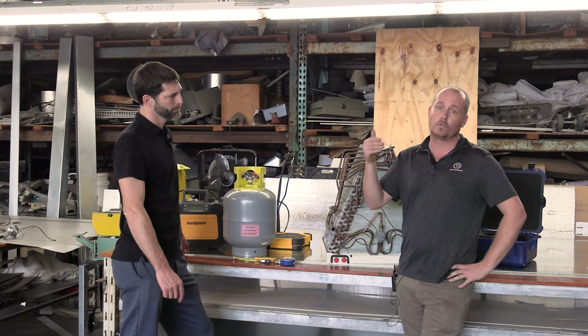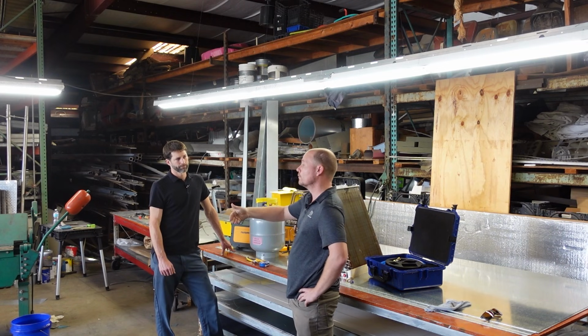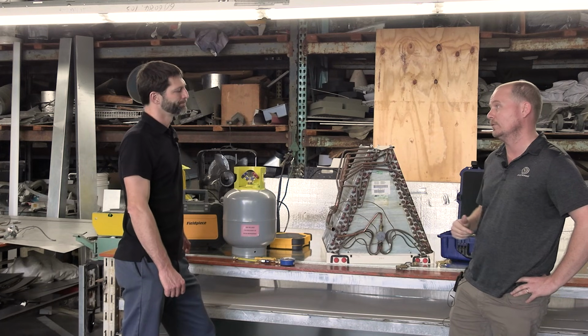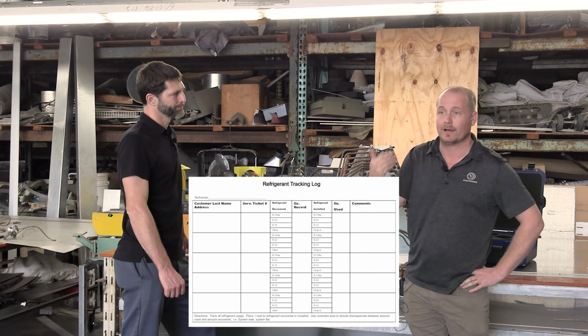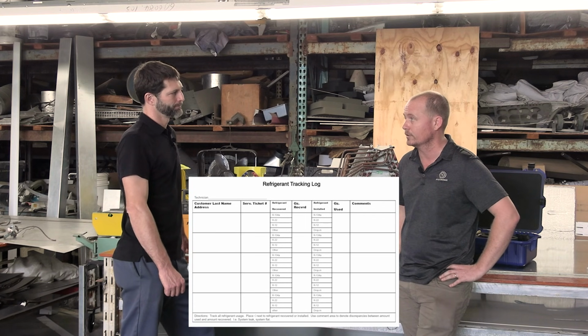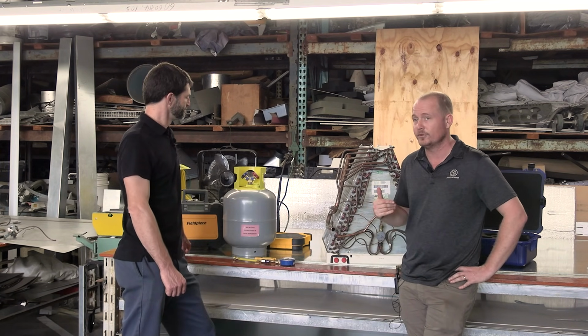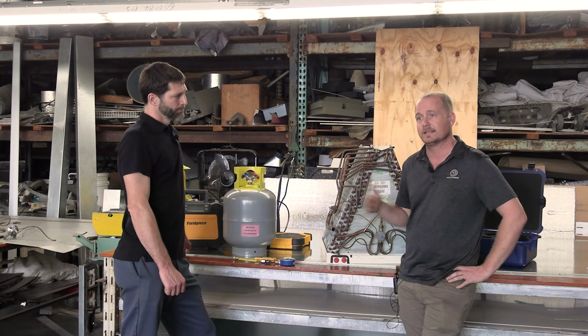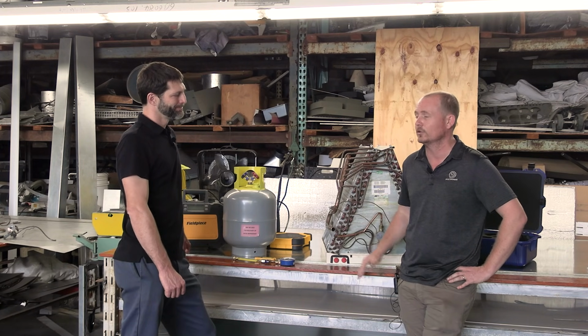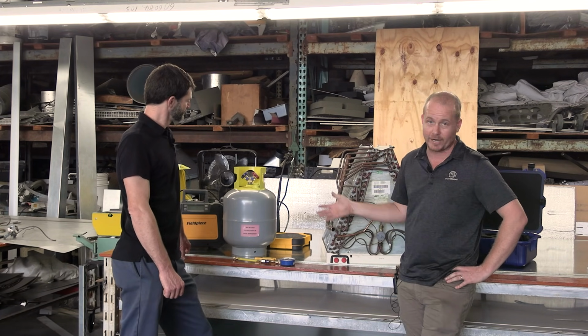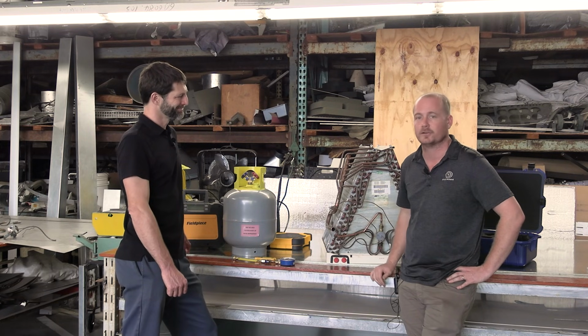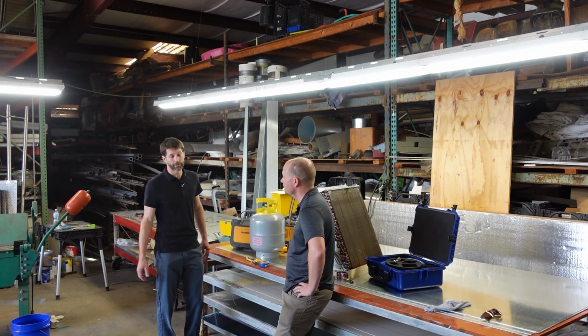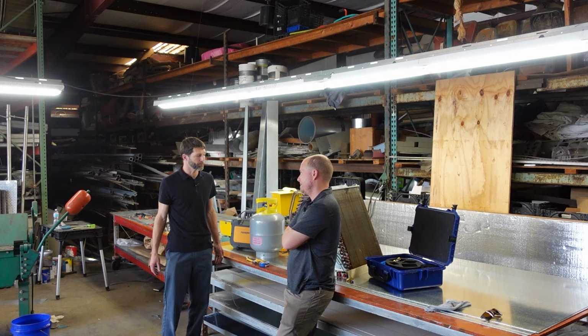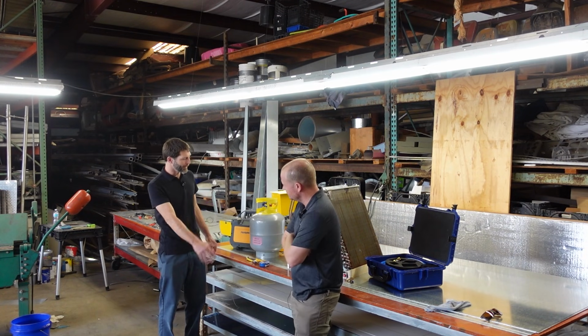If you are working in cases where you are removing systems from commission, you also need to keep a logbook of how much refrigerant you took out of that equipment, where it came from, and the models and serial numbers of that equipment. So you have to have some way of doing that. In regular service, that isn't necessary for the smaller stuff that we work on, but it's just a good idea to do anyway. You're keeping tabs on yourself. Yeah. So that's the newest update to the EPA 608 standards. So we just want to make sure that we're in compliance and we're prepared.